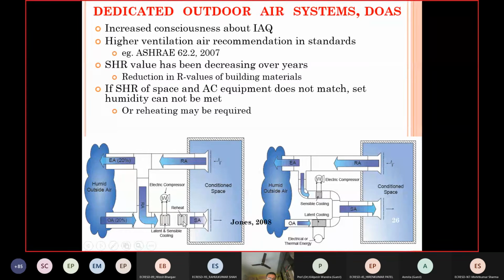And it is shown then that sometimes when your SHR is low, to remove moisture, you may have to overcool the air here, so that you are able to take out the required amount of moisture. But then the temperature may become too low in doing that, so you may have to reheat it so that it doesn't go to a very low temperature, and it is at a temperature where you can supply it into the conditioned space. Right. So this is one possible disadvantage. Of course, this is like a very irrational waste of energy, and hardly utilized here. Only for very precise control, this might be needed.